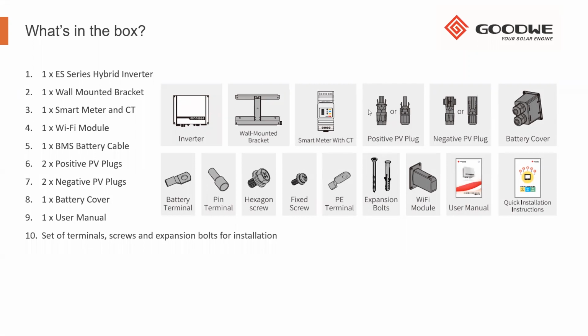As you'll see, we give all the correct MC4s and connectors for the inverter itself, so it's always recommended to use the provided connectors. If you use other connectors and it does lead to a failure of the connector, unfortunately we can't assist much with that. We also have the battery cover and the AC cover, so it's 2 covers that look like this. One is for the battery terminal and the other for the AC terminal. We do include a few lugs for your battery cable connections, your AC cable connections, and your neutral connections. With the ES inverter, the Wi-Fi module is separate and needs to be installed separately, whereas some of the other models you will find it already installed.